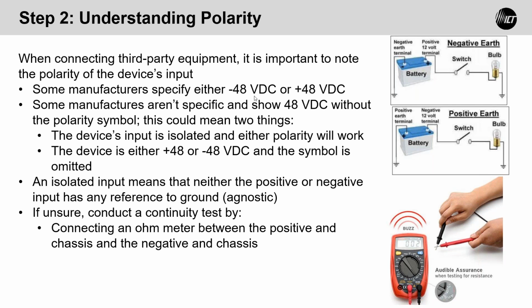Sometimes they don't tell you. Sometimes they'll just say it's 48 volt DC without putting a polarity symbol. This could mean a couple of things: it could mean the device's input is isolated and either polarity will work, whether plus or neg 48, and they've left the symbol out. That's often the case, but you don't want to take that for granted.